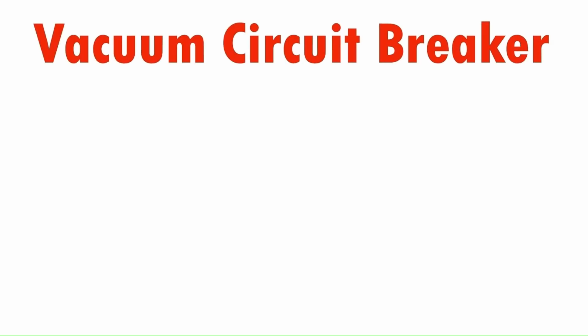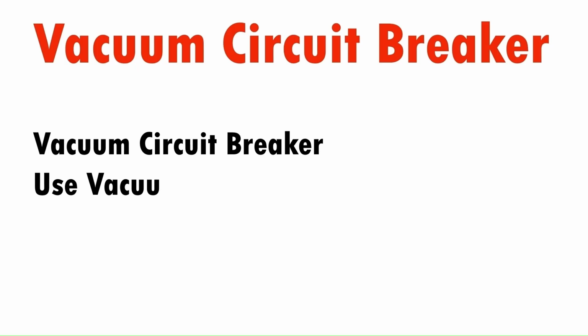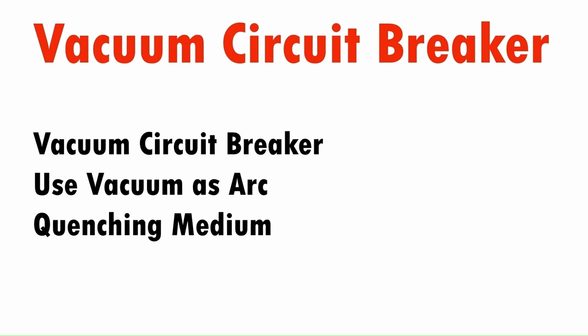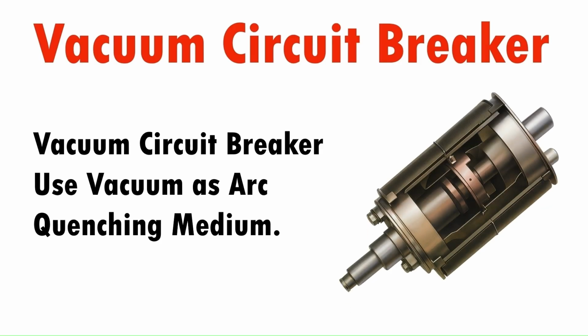Hi, today we will learn vacuum circuit breaker. Vacuum circuit breaker uses vacuum as arc quenching medium. In this circuit breaker, the fixed and moving contact is enclosed in a permanently sealed vacuum interrupter. It is mainly used for medium voltage ranging from 11 kV to 33 kV. Vacuum circuit breaker is generally not preferred for applications beyond 33 kV.